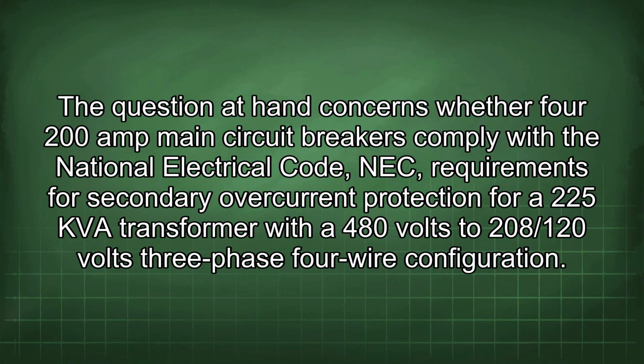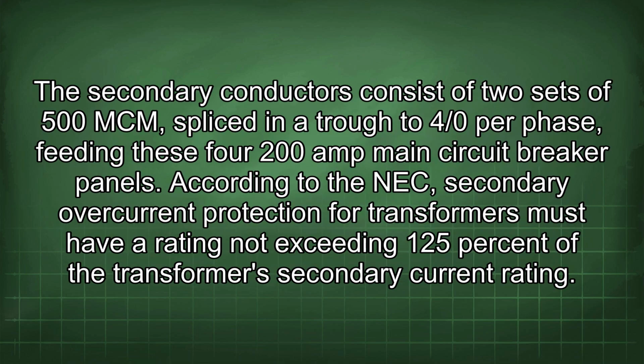The question at hand concerns whether 4 200-amp main circuit breakers comply with the National Electrical Code (NEC) requirements for secondary overcurrent protection for a 225 kVA transformer with a 480 volts to 208/120 volts 3-phase 4-wire configuration. The secondary conductors consist of two sets of 500 MCM spliced in a trough to 4/0 per phase, feeding these 4 200-amp main circuit breaker panels.